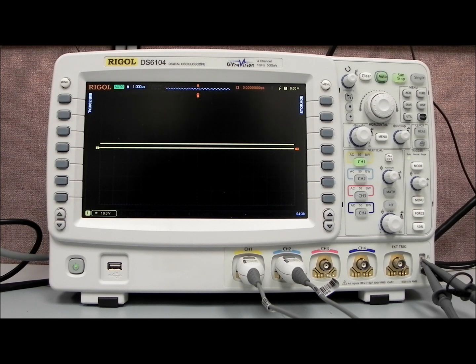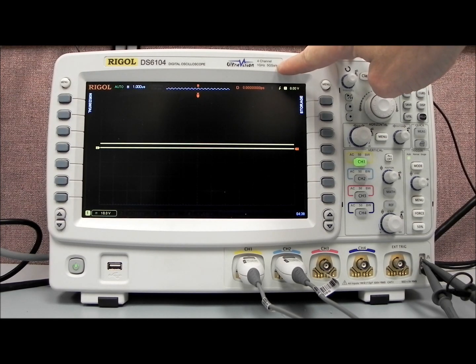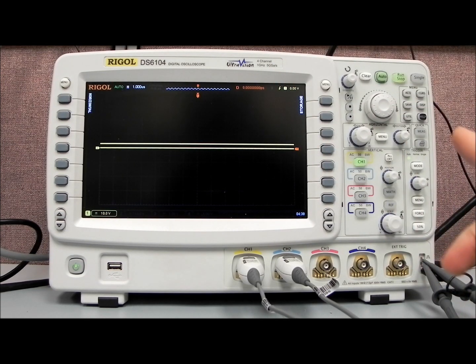This particular model that we have in front of us is the DS6104. The 6104 is a 1 GHz scope capable of 5 gigasamples per second sample rate, and it has 4 channels. So the 6104 denotes the 1 GHz, and then 4 denotes the number of channels available to us.